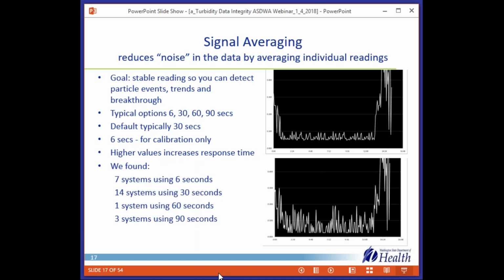Here's what we found. 7 systems had turbidimeters set for 6 seconds. So they were seeing some erratic results. 14 systems were using the default value of 30 seconds. 1 system was using 60, and 3 had it set at 90. Now, the operators in general hadn't been involved in setting up their equipment, and so they didn't realize that these settings were there, and they didn't know why they'd been set that way.